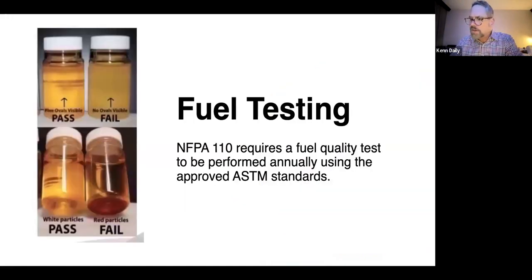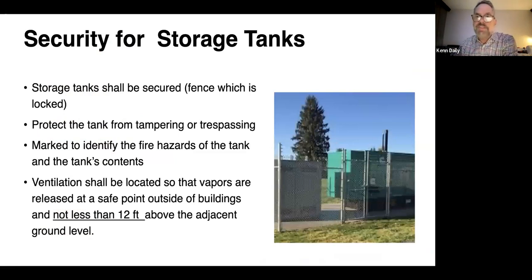Fuel testing once a year, they said. You have it fuel tested and hopefully you have to show a passing test. Fuel tank storage, you must have a fence. NFPA 30 requires fuel storage to be protected. So that fence around it, mostly it's 6 feet, metal chain link fence, has to be non-combustible, of course, can't be wood. And then that is locked, it's maintained locked.